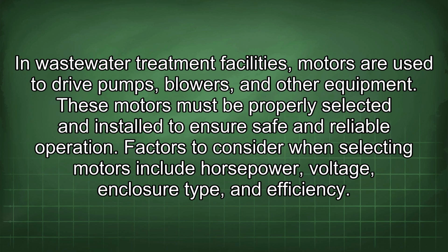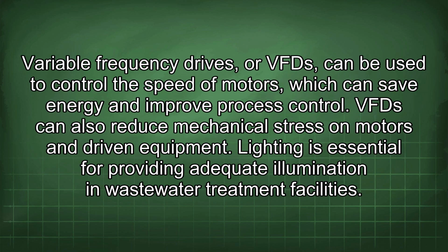In wastewater treatment facilities, motors are used to drive pumps, blowers, and other equipment. These motors must be properly selected and installed to ensure safe and reliable operation. Factors to consider when selecting motors include horsepower, voltage, enclosure type, and efficiency. Variable frequency drives, or VFDs, can be used to control the speed of motors, which can save energy and improve process control. VFDs can also reduce mechanical stress on motors and driven equipment.